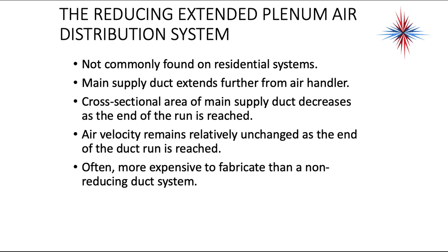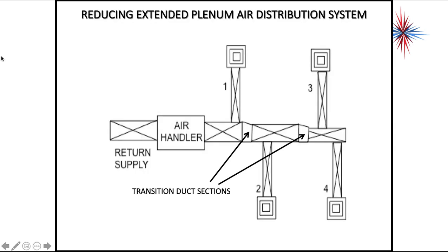In other words, the area gets smaller. This forces the air velocity to remain relatively unchanged. If we decrease the area of the ductwork and maintain our airflow, our velocity is going to stay the same. It's a more expensive situation to fabricate than the non-reducing duct system. What happens is after every takeoff, we reduce the size using a transition duct section to decrease the area of the ductwork — decrease the size. When we decrease the area, we're forcing the airflow through a smaller area of duct, which increases the speed.